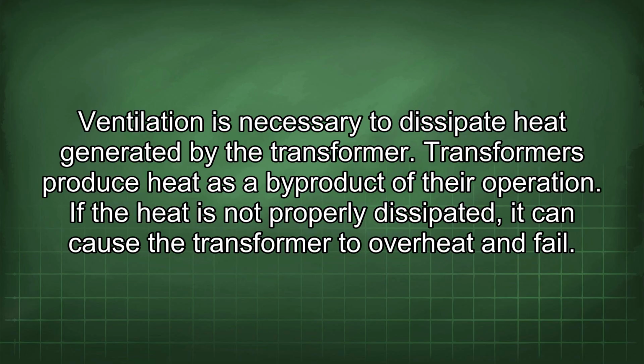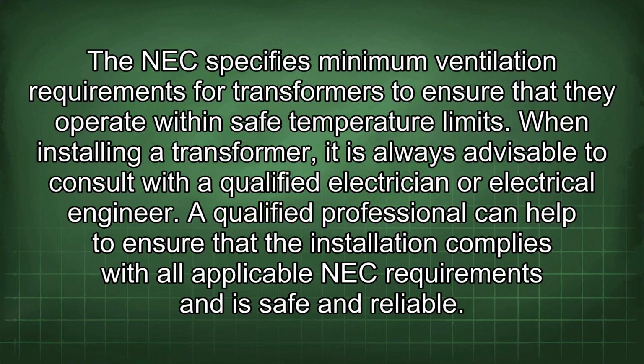Ventilation is necessary to dissipate heat generated by the transformer. Transformers produce heat as a byproduct of their operation. If the heat is not properly dissipated, it can cause the transformer to overheat and fail. The NEC specifies minimum ventilation requirements for transformers to ensure that they operate within safe temperature limits.